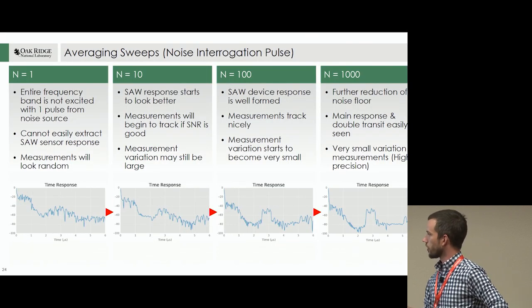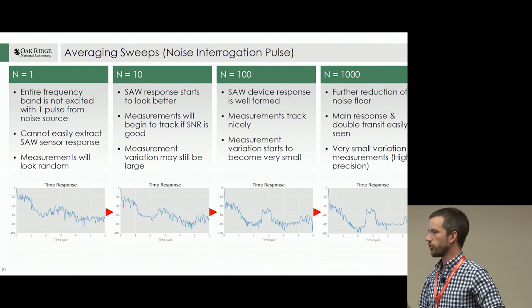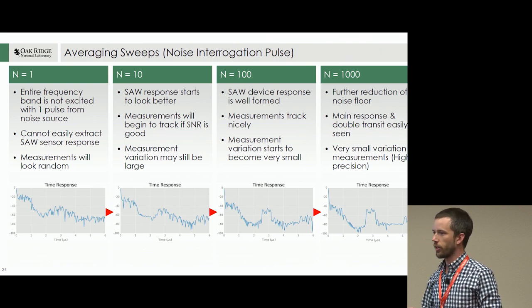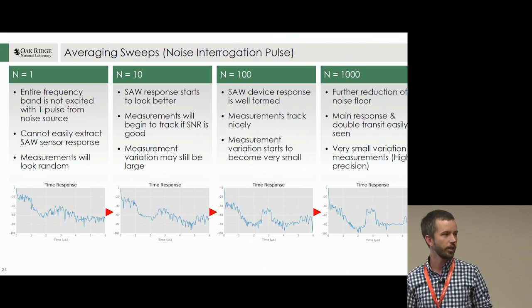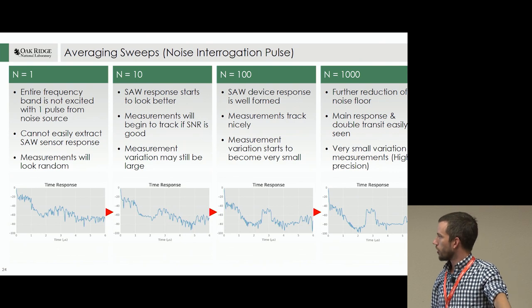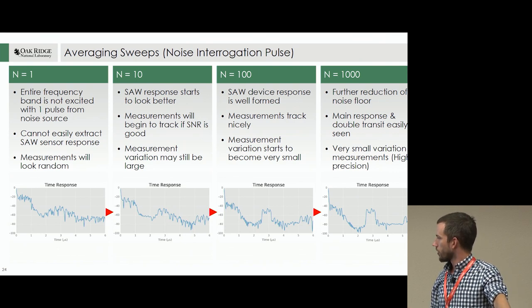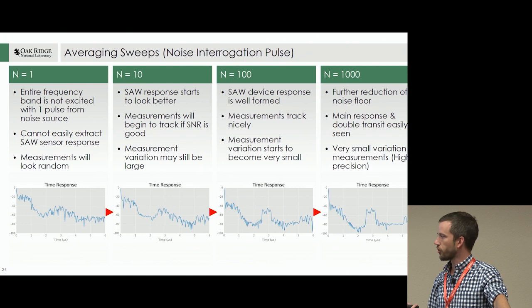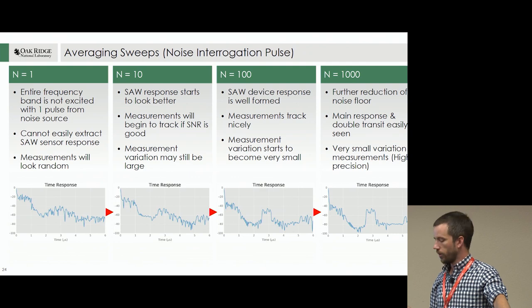Here's what these signals look like as we're averaging — from 1 to 1,000. At 1, you get this spread out, noisy-looking signal with very high variation. Up to 1,000, you push your noise floor down, your sensor signal starts to come out, and you get a very stable measurement. For temperature, it can be a couple tenths of a degree to hundredths of a degree precision.